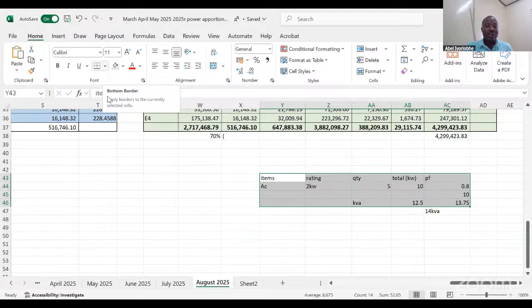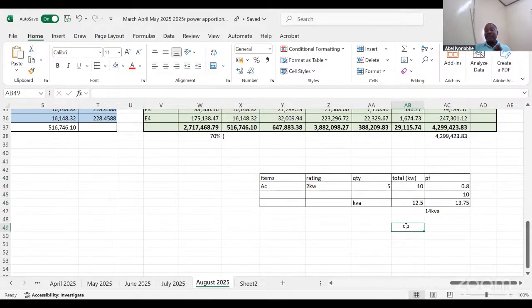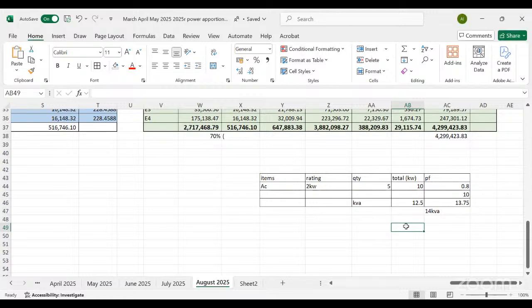The load that is already in the building. In case the entire load is higher than the size of generator that you have, you can now say, this is the reason why our generator is shutting down when it attains its full load capacity. So in this case, you have data to convince your management to go for 15 kVA. Nobody will argue this. Is it clear? Yes, sir. All right.